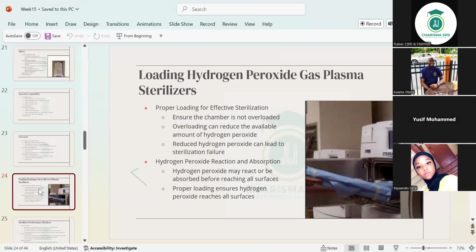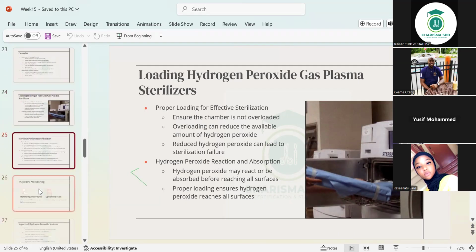So proper loading for effective sterilization. Ensure the chamber is not overloaded. Overloading can reduce the available amount of hydrogen peroxide. Reduced hydrogen peroxide can lead to sterilization failure. Hydrogen peroxide reaction and absorption: it may react or be absorbed before reaching all surfaces, which is something that we don't like. So proper loading ensures that the hydrogen peroxide reaches all surfaces.